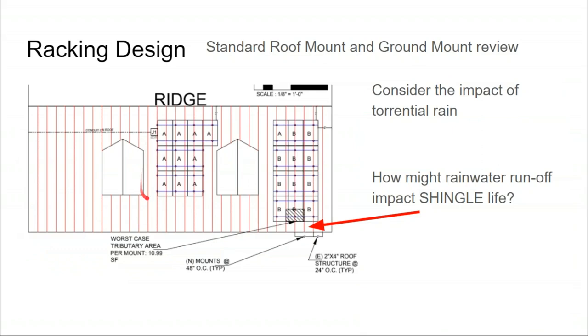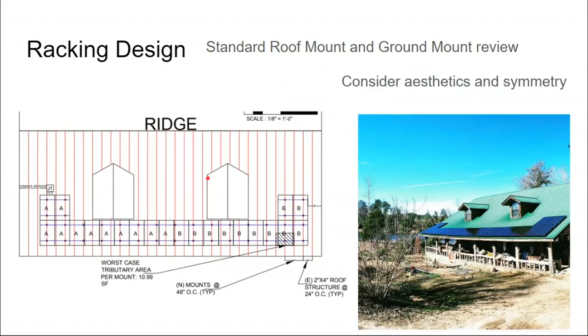Another difference is this design called for subarray subsections, which would have required either ugly conduit going across the rooftop or an internal conduit run between sections. An internal conduit run means putting a hole in the roof, and two subarray sections means two holes. This is a metal roof, so we don't want to do that too much. I love internal conduit runs because they look so much better, so we made it one continuous array to avoid the jump between subarray sections. Down at the bottom of the roof, in the attic section, is where we drilled into the roof, piped it, and flashed it.